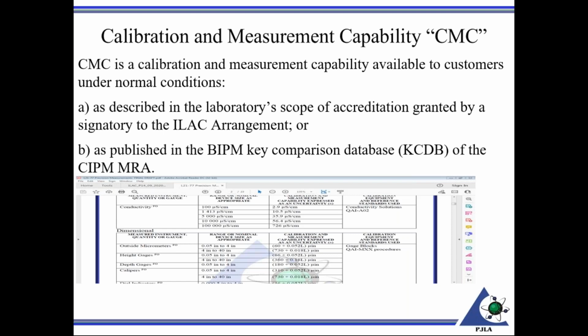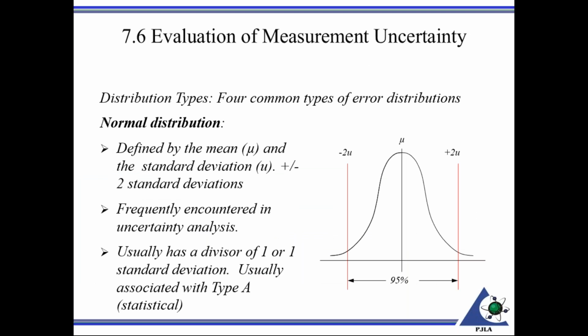So when you're doing your uncertainty budget, particularly for an initial accreditation, you want to consider, what is the best device we're going to calibrate? Of course, your standard should always be of higher accuracy than the unit under test. So for example, if you have a temperature standard of 0.001 degrees, you're not going to test an unknown that has that same resolution. So you want to at least perhaps go out to 0.01 degrees and then figure out an uncertainty budget based on that. And that is a published CMC. For a calibration lab, that's off the scope of accreditation when you see that, or it could also come from the NMI, like NIST, for example, which is captured in the BIPM key comparison database. So again, looking at those distributions in a little more detail here. The normal distribution is depicted over there.